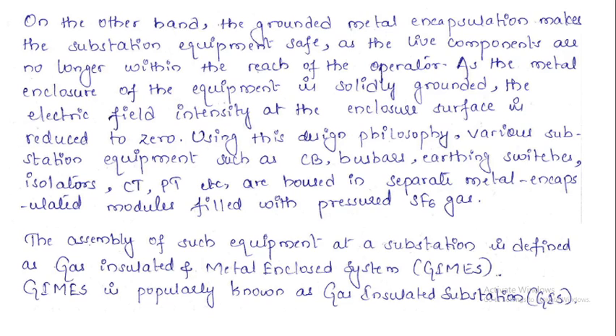Using this design philosophy, various substation equipment such as circuit breakers, bus bars, earthing switches, isolators, CTs, PTs, etc. are housed in separate metal encapsulated modules filled with pressurized SF6 gas. In a normal air insulated substation, all these protective devices are directly exposed, with air acting as the insulation medium. But in order to overcome the problem of oxidation as well as corrosion, the gas insulated substation is used, where the gas mainly used is SF6 gas. All these protective devices are housed in separate metal encapsulated modules, fixed in a building on the floor, where pressurized SF6 gas acts as the insulating medium.